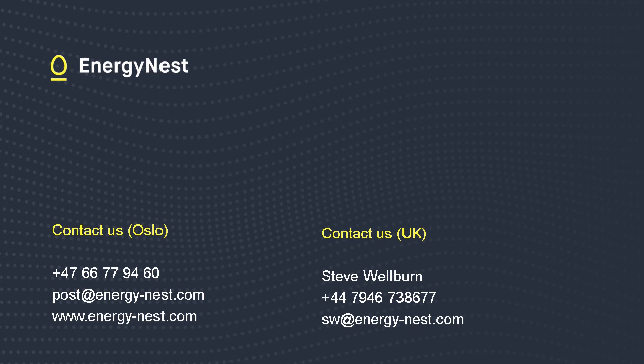It depends entirely on application because the higher the temperature, the more insulation material you need. If you were to look at systems that would operate with daily cycles, accumulating energy over 12 hours and discharging over 12 hours, it's different from a system that's operating with 3 to 4 hours and discharging much, much later. You need to insulate it better. Typical insulation thickness is 300 millimeter to 600 millimeter insulation.